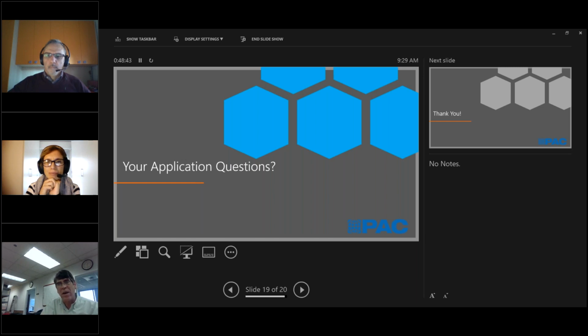From a maintenance standpoint, that could take 5 minutes, and it's very simple to do. Okay, and the sensor can be installed vertically, horizontally. There are some restrictions. We recommend from 9 o'clock to 3 o'clock. One thing you would not want to do is to install it upside down, because if there are any entrapped air bubbles, they travel up and might not be able to come out. In cases where there are some particles potentially in the fluid, you would want to install it horizontally. That'll allow the particles to flush out from the piston movement.